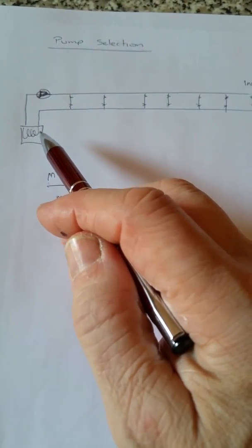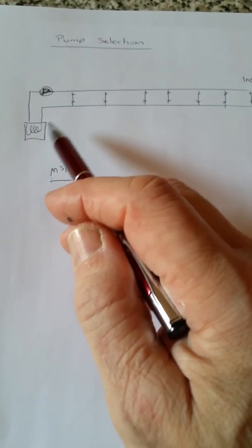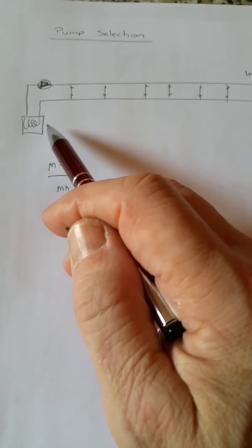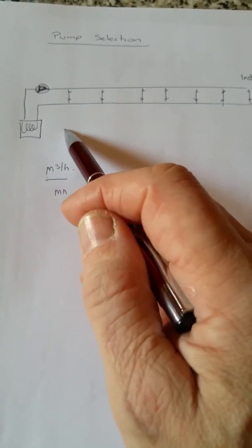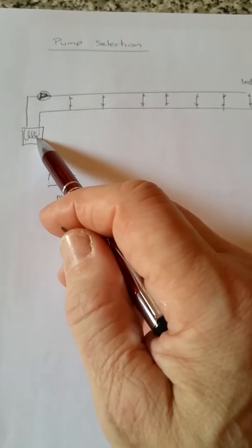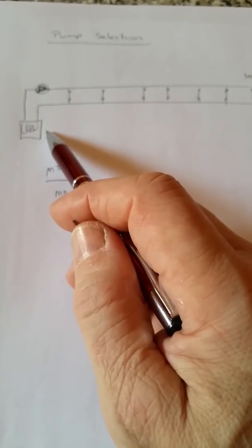You're going to get some clues back at the boiler here. So if you haven't got adequate flow through the system and you get a full load situation, your delta T here is going to start getting bigger. So this is going to be a good clue. If your DT can't be got correct here, under full load, then all you've actually done is spread out an incorrect flow rate across the system.